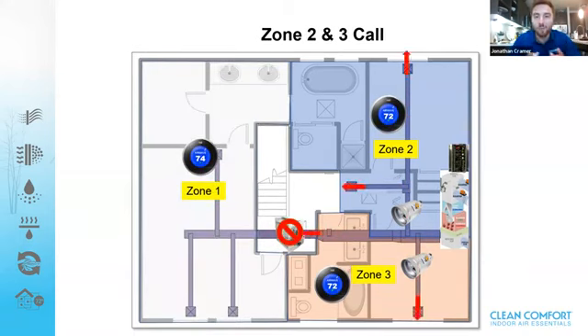But let's say zone 1 says, hey, you know what? I'm good at 72. I don't want that. I want it to be at 74. It's a little cold in here. So now we only have 2 zones calling out of the 3-zone system. As you can see, the red arrows are picking up. They're getting a little bit faster. Maybe the people in zone 2 and 3 are noticing that it's a little bit louder when it's running. It's uncomfortable. Something doesn't sound right like it did before, when I didn't have zoning equipment.